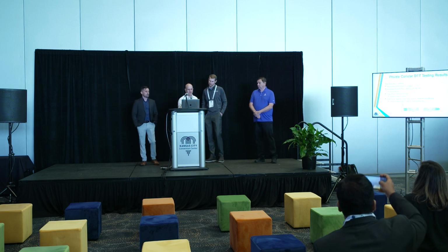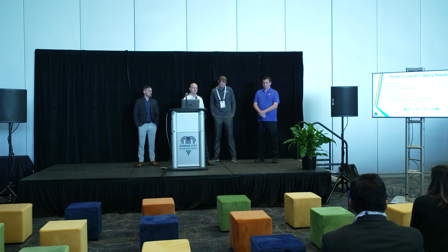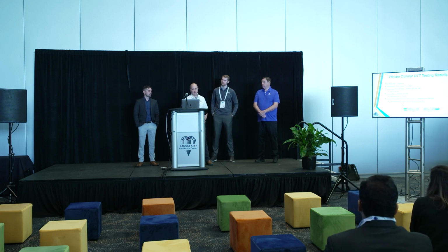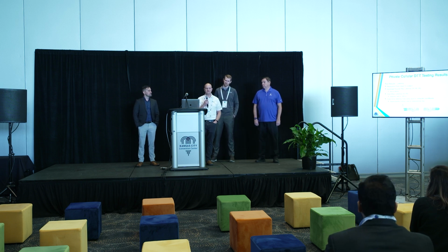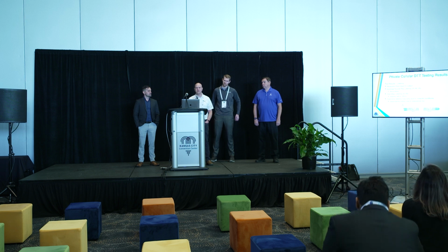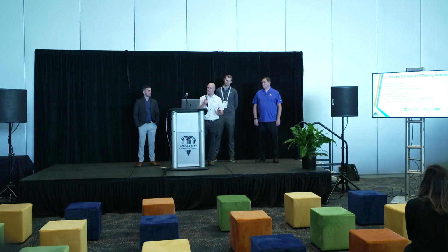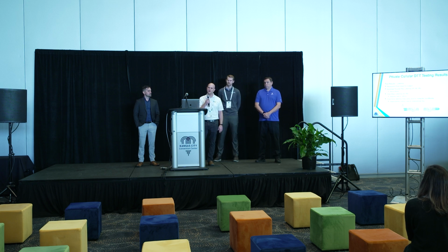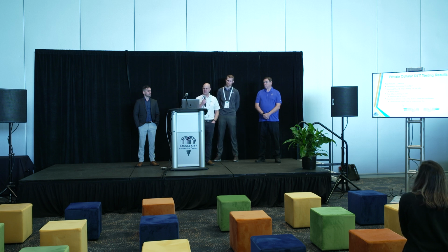Sure. As I mentioned earlier, dependability is one of the critical performance characteristics of this type of system. The way we did this was we measured the amount of time it takes to send a DTT signal from A to B, and then we hairpinned it and sent it back to A. That way we had a common time reference at A, and we could measure a complete round trip time. Then you can divide that by 2 to understand what your one-way A to B time was. Nominally, we had around 80 milliseconds round trip, so 40 milliseconds. I think Kevin said about maybe 35 in some cases.